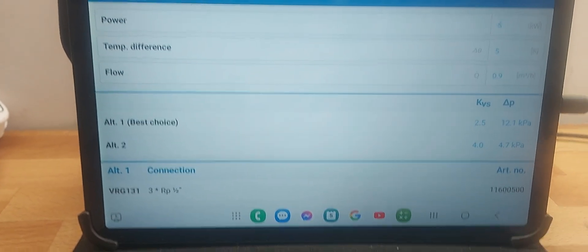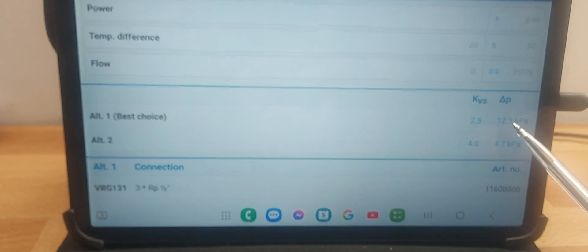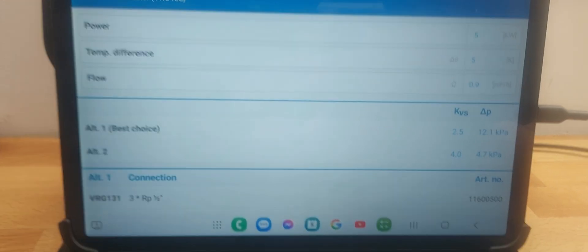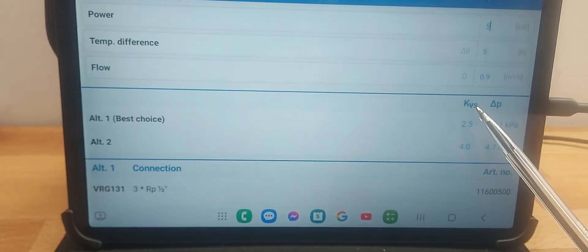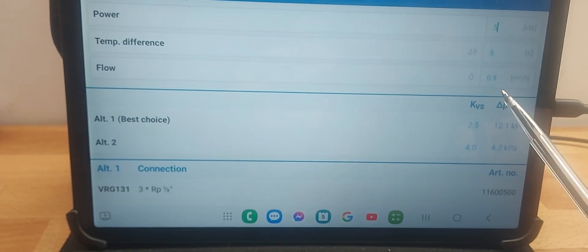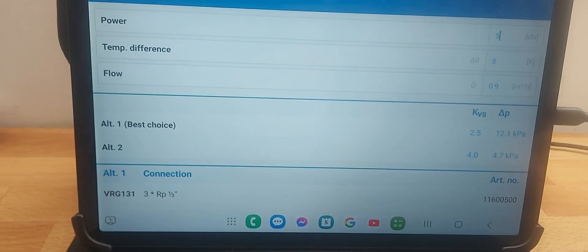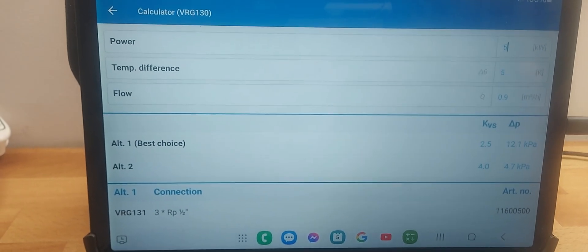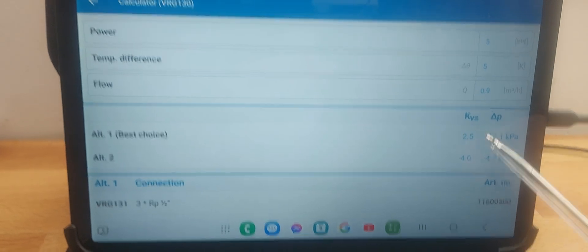I use the estimated pressure drop. There could be some errors here - they've worked out there's some tolerance and leeway in the valve. They're showing an alternative valve with a kvs of 4.0. Just to remind anyone: the kvs value is the flow in cubic meters per hour that leads to a drop of one bar across a valve. So if you're pushing water through a valve with a pressure differential of one bar, measure that flow in cubic meters per hour and it gives you the kvs value.